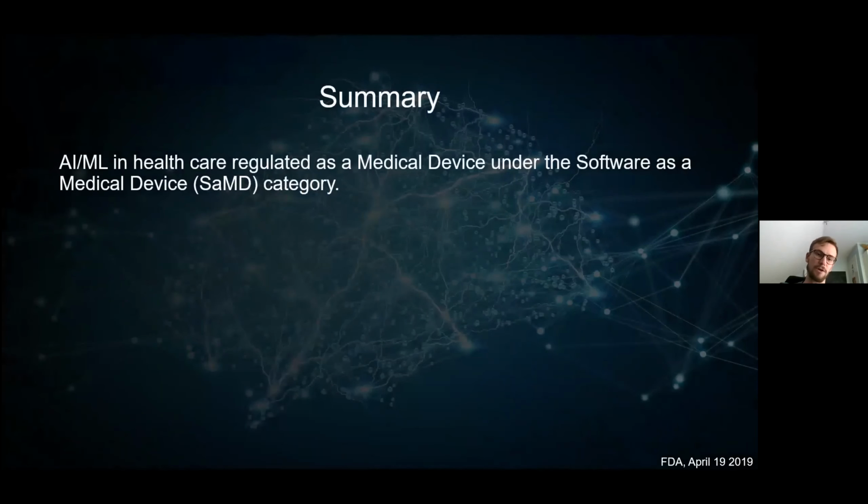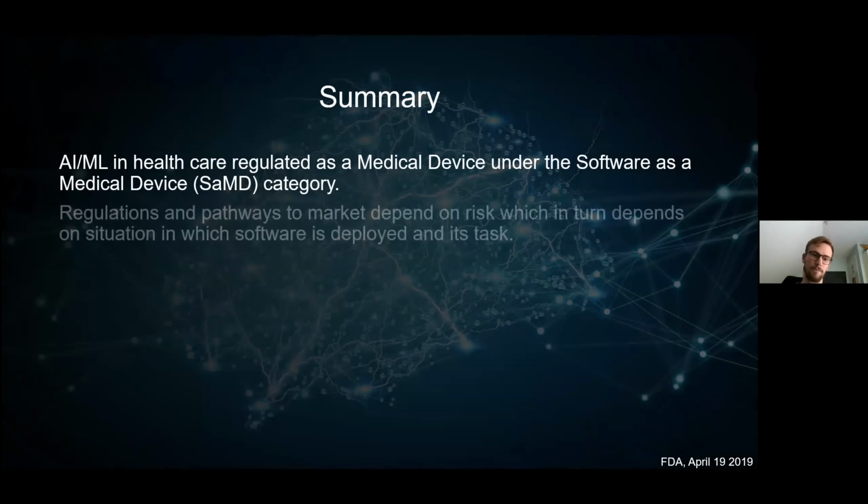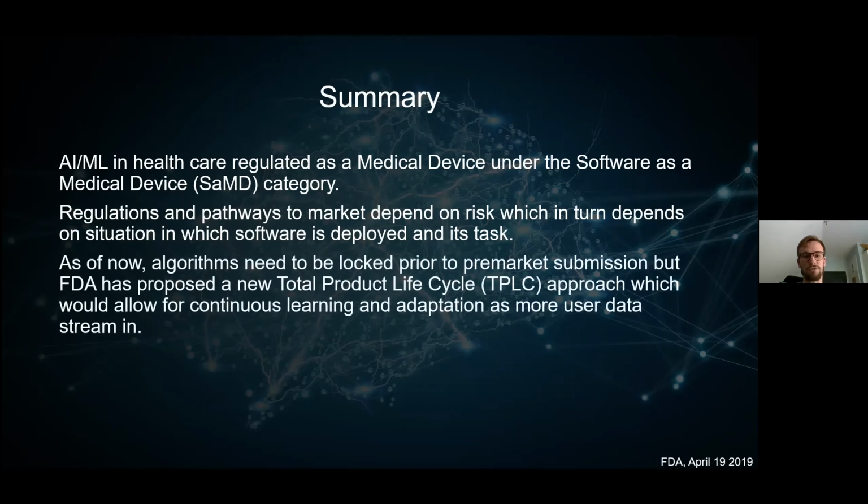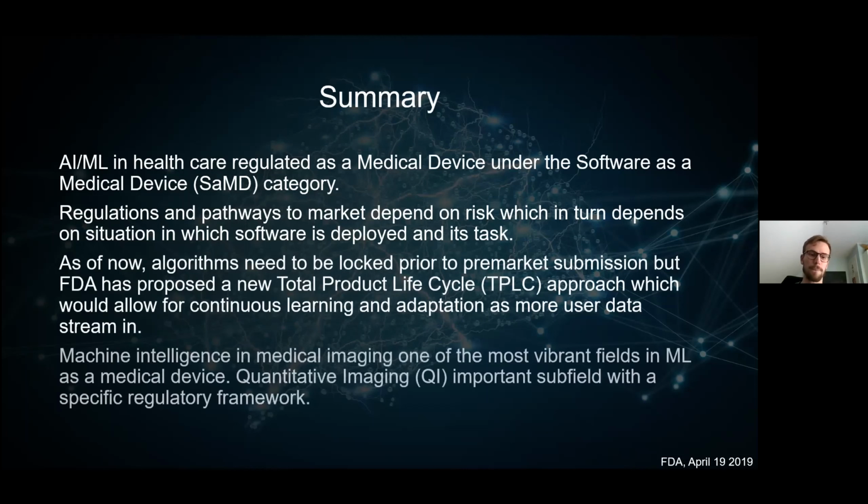So to summarize, machine learning in healthcare is regulated as a medical device under the Software as a Medical Device, SaMD, category. Regulations and pathways to market generally depend on risk, which in turn depends on the situation in which the software is being deployed and its task. As of now, algorithms need to be locked prior to pre-market submission, but the FDA has proposed a new total product lifecycle, or TPLC, approach, which would allow for continuous learning and adaptation as more user data comes streaming in. Machine intelligence and medical imaging is one of the most vibrant fields in machine learning as a medical device. Quantitative imaging, or QI, is an important subfield here with a specific regulatory framework that I mentioned.